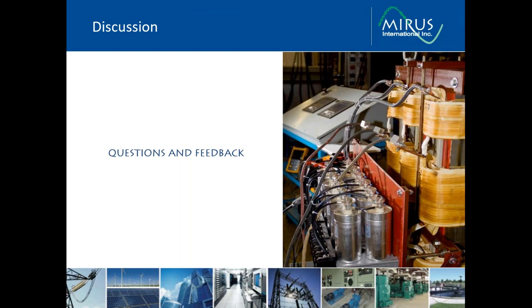They will generally use thyristors to convert AC to DC. The DC is where the batteries are connected. So we charge the batteries and discharge through the DC, and then we go through inverters and supply the loads. Because there's a demand to limit harmonics, most UPSs are built with some kind of input solution, sometimes active, sometimes passive. If there's a UPS application that doesn't have harmonic mitigation, then the wide spectrum filter can be applied.